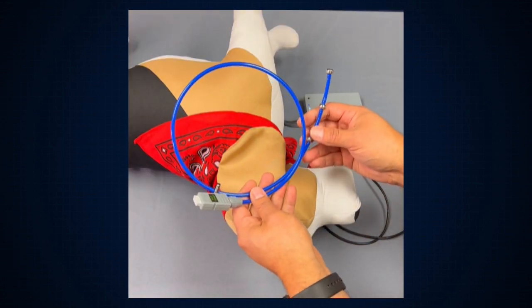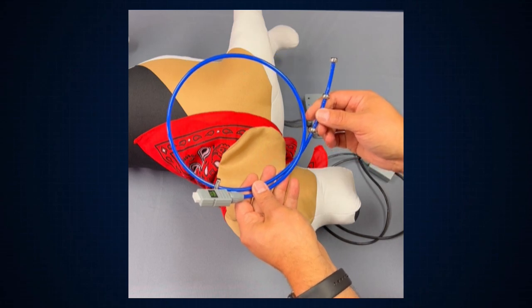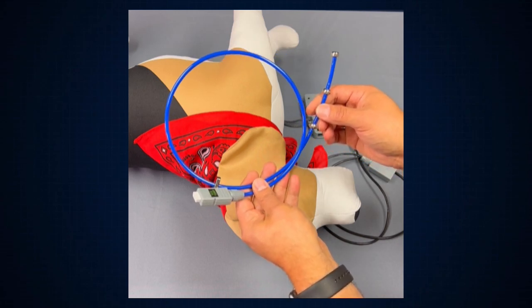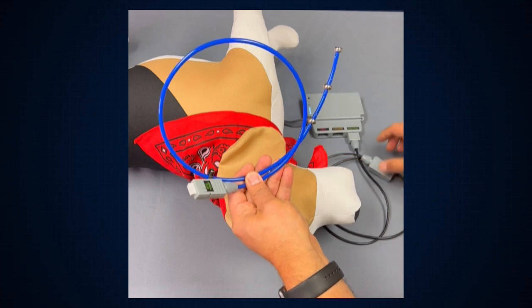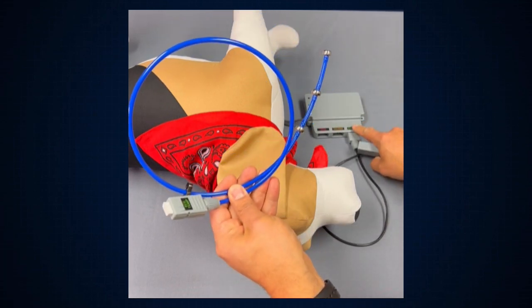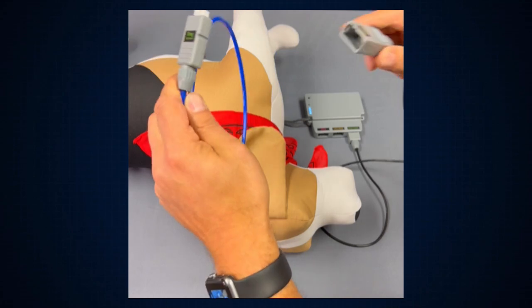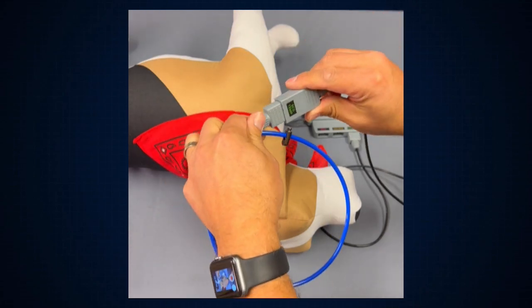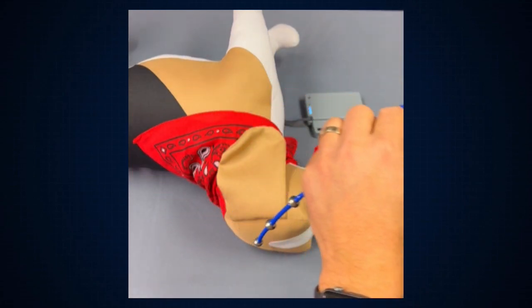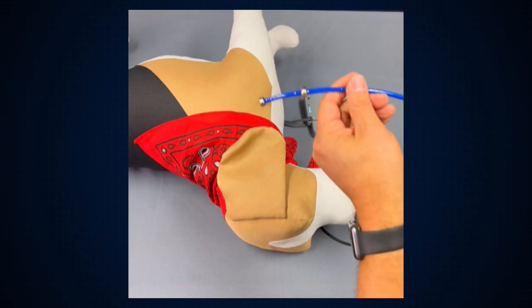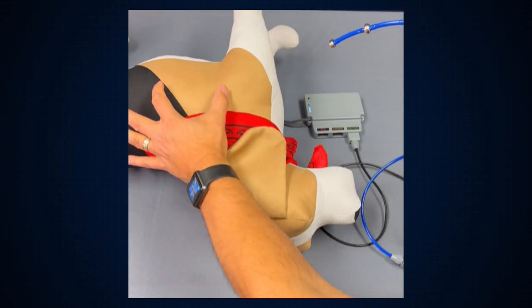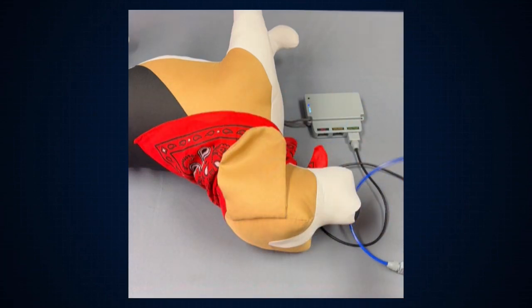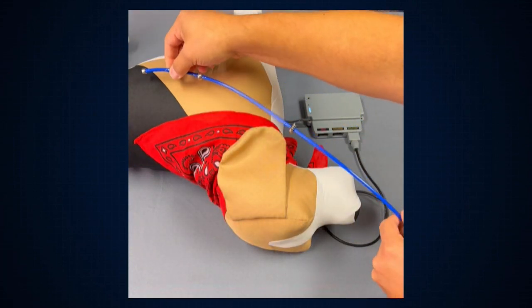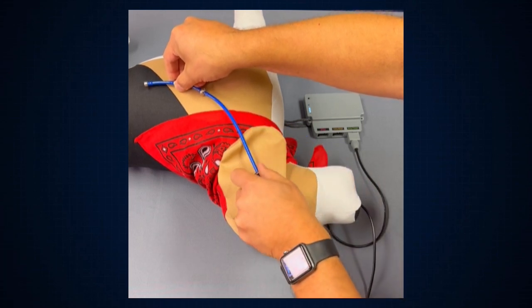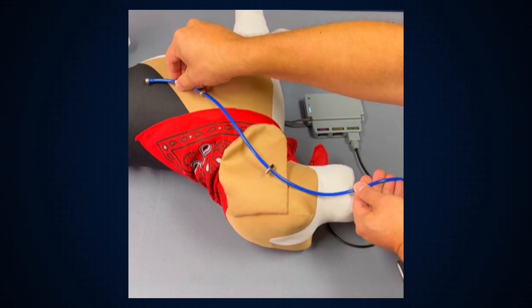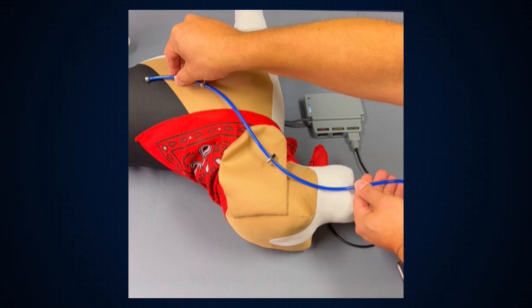To utilize an esophageal ECG temperature probe, go ahead and choose the probe based upon the weight of the patient. Simply plug the probe in, again, either into the port directly on the module or into the end of the extension cable, just like so. What you then want to do is take a look at the patient, go ahead and determine about where the heart of the patient is, take the esophageal probe, lay the center contact on the outside of the patient's body, and run the PVC material loosely along the esophageal line, again on the outside of the patient's body.